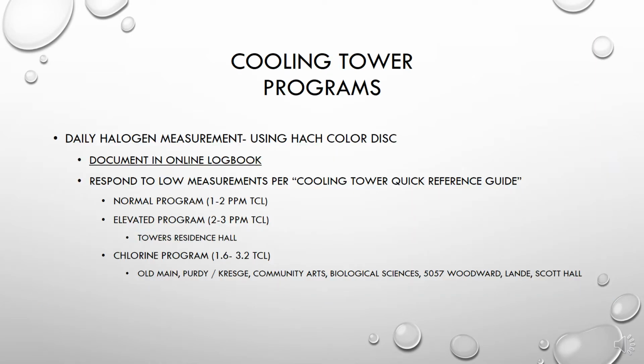Just a reminder of the cooling tower programs we have on campus. Peter covered them earlier in the training. Like I mentioned, we have that daily halogen measurement and recording it in our online logbook. And we are responding to low measurements per the cooling tower quick reference guide that's posted at each controller. Each controller will have a quick reference guide that matches the program it is running. Whether that's the normal program, the elevated program, or the chlorine program will depend on which building it is.